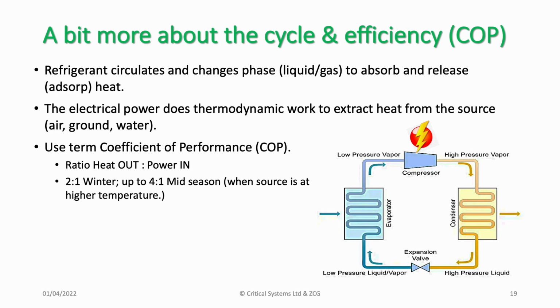It should not be expressed as an efficiency. So sometimes I see this heat pump is 300 or 400% efficient. That's not a correct statement. Its coefficient of performance is somewhere between 2 and 4 to 1, depending on the operating conditions.